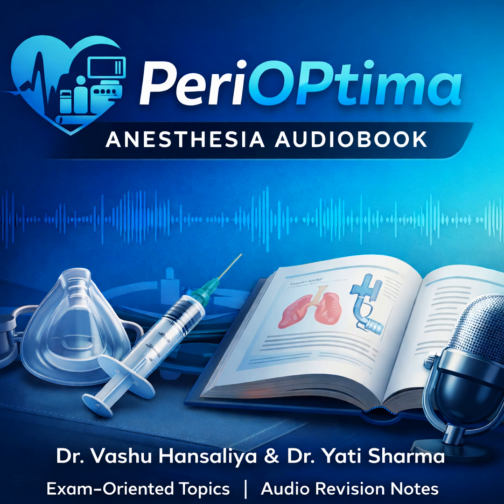That brings us nicely to the medical gas pipeline system, or MGPS. We have PISS for cylinders. What's the equivalent for the pipeline? For the pipeline, we have the Diameter Index Safety System, or DISS. In some regions, you might also see NIST, which is non-interchangeable screw threads. The concept is the same.